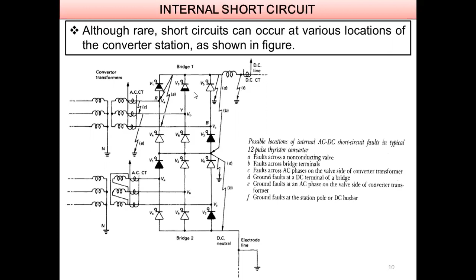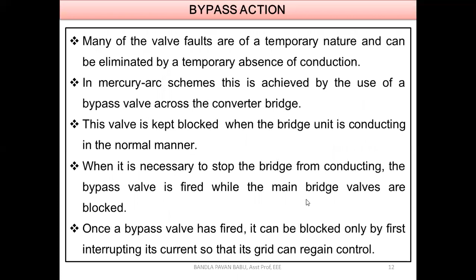So earlier we have seen, look at this diagram. Suppose the fault is very near to the conducting valve, suppose 1 is conducting there. Then obviously we are going to choose these two valves. Suppose the fault is very near to 3 and 6, and 3 is in action, then we are going to prefer 3 and 6 as a bypass pair. Suppose 5 and 2, so 2 is completely on, then we are going to prefer 2 and 5. If suppose 1 and 2 are in action, then we can prefer 3 and 6, because at the next instant 3 is partially on there, so 3 and 6 is also preferred. So what I would like to conclude here is that it depends upon the origin of the fault. It is not mandatory that first and fourth should be used as a bypass pair.